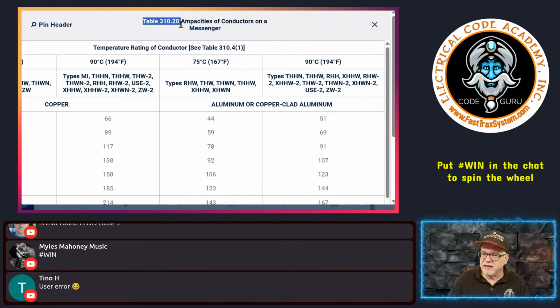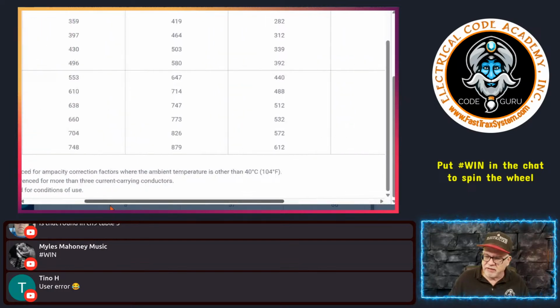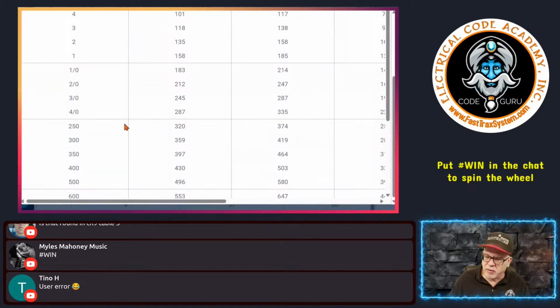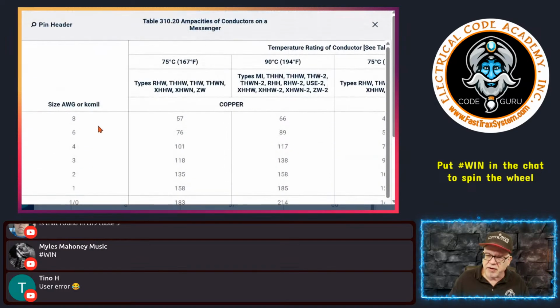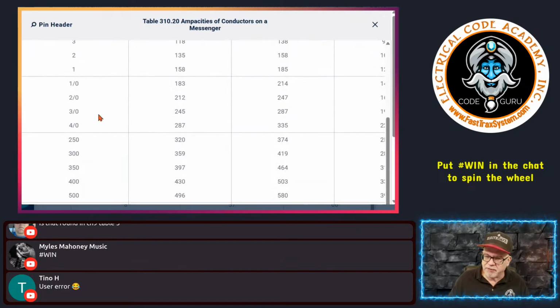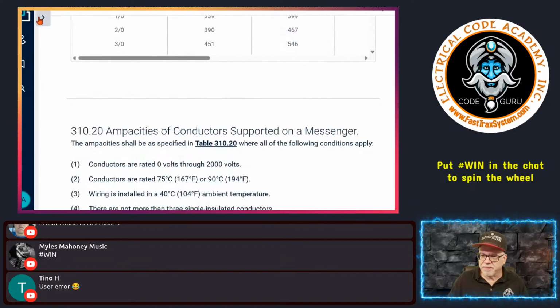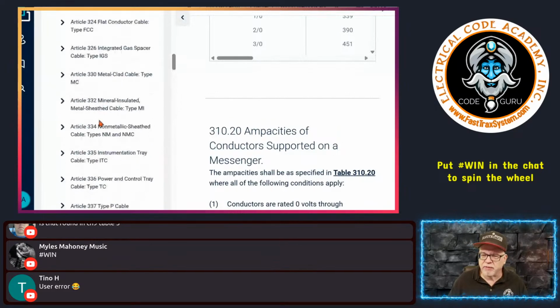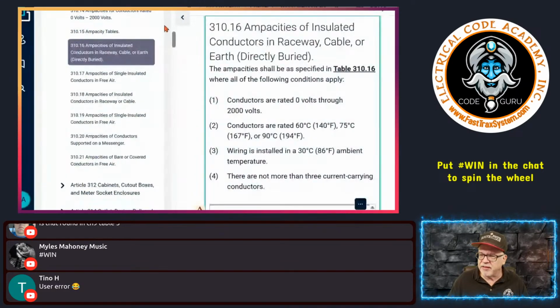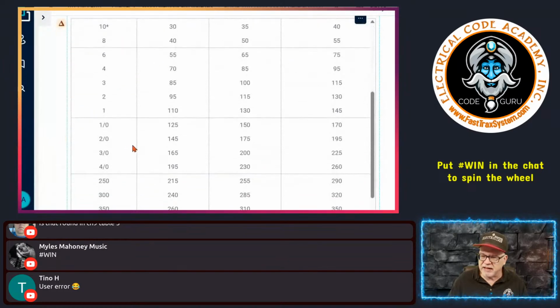So here you see, this is the ampacities of conductors on a messenger. And it can affect the ampacity of the conductor. For example, I come down here and we just look at something that we're familiar with. Here's a 3-aught, 3-aught copper. So the copper over here under the 75 for 3-aught is 245 amps, okay? Now, under 310.16, what would that be? Just so you can compare, 3-aught under 310.16 is good for 200. So you're getting extra amps based on messenger.